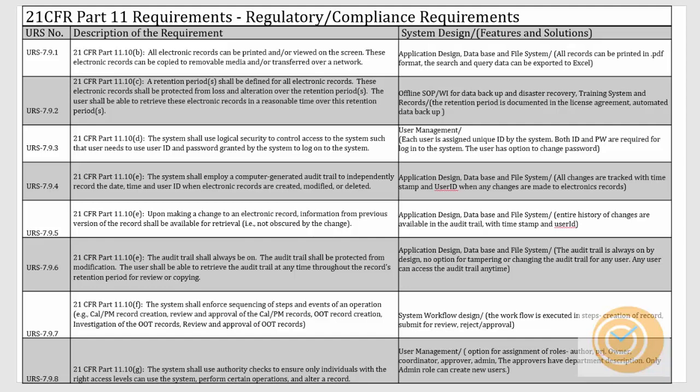And you should use logical security to control access. So the user ID and password would be required to log into the systems. The system shall employ computer generated audit trails independently to record the time, date, and user ID. So when the user is using the system, any changes being made by the user should be tracked in an audit trail. And again, the audit trail should be a permanent record, and no one should have access to make changes to that audit trail.